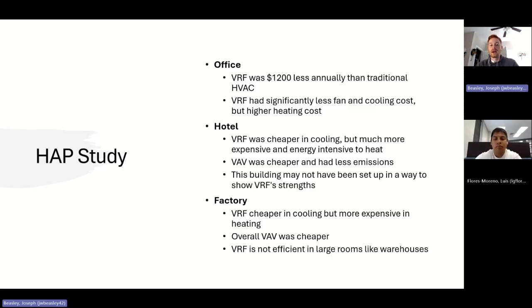Now, the hotel had cheaper cooling in VRF, but overall, VRF was much more expensive for the hotel. And I think that's because it wasn't set up correctly. I wasn't able to get all the different rooms implemented into that building. So that alternative, I think, was a little bit flawed. In real life studies, they've studied real hotels, and VRF does save money, and it is less energy intensive for hotels. And then in the factory, which is just a large building, the VRF was more expensive because of the extra pipes and extra installation costs, because it's not as efficient in large warehouses like that.